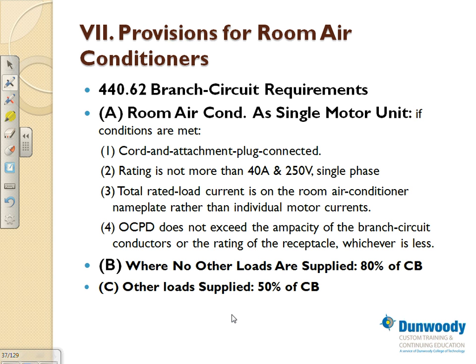less. So if I have a 20 amp circuit breaker and a 15 amp receptacle, now you're limited to 15 amps because the air conditioner plugs into a 15 amp receptacle. So whichever is smaller.